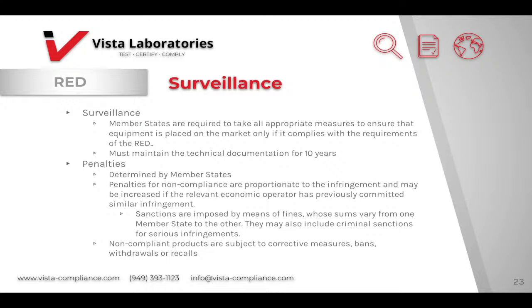So moving on to surveillance under RED, member states are required to take all appropriate measures to ensure that equipment is placed on the market only if it complies with the requirements of the RED, and it must maintain the technical documentation for 10 years. For penalties, this is determined by member states.